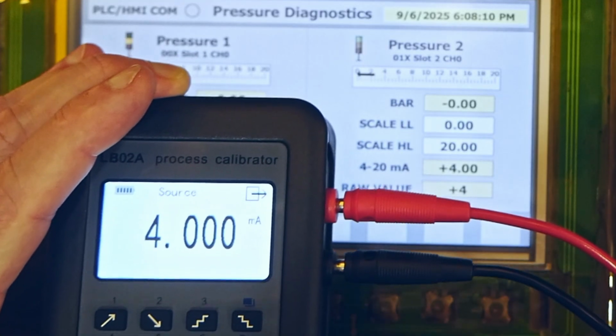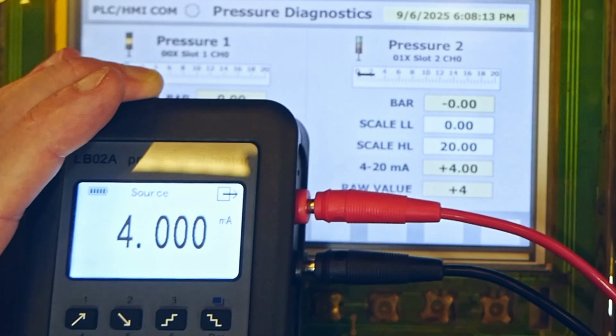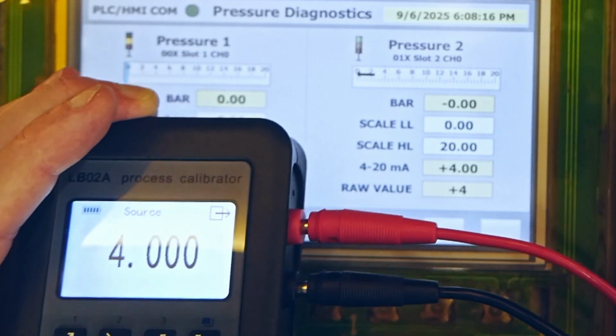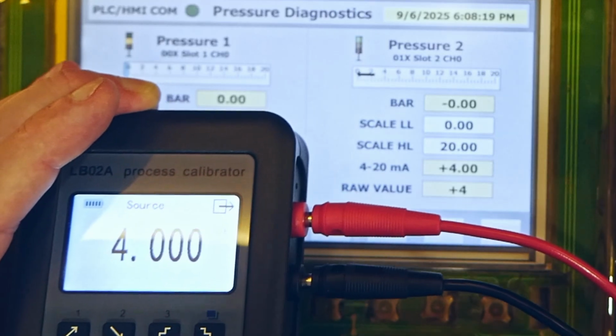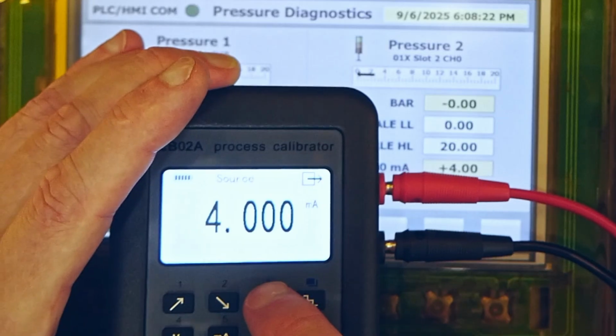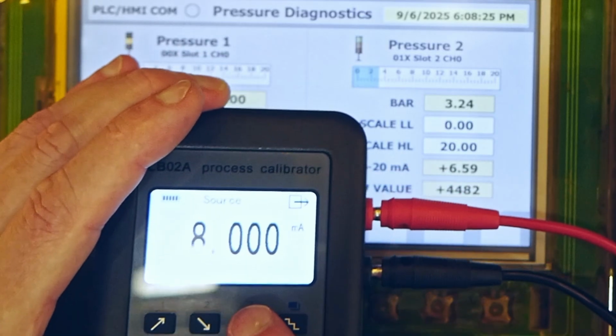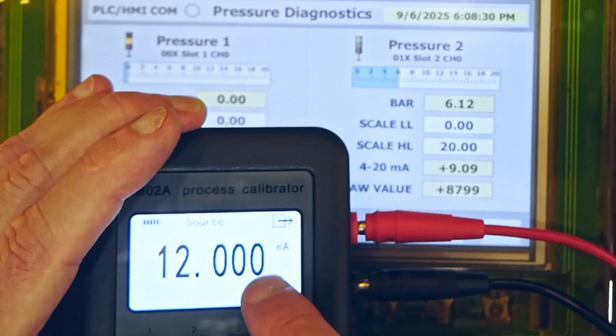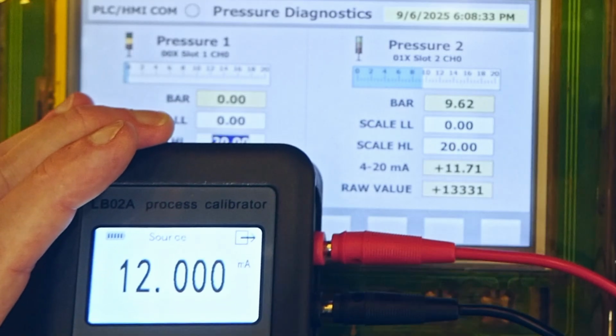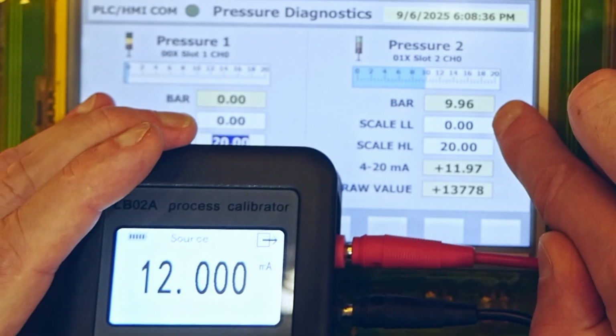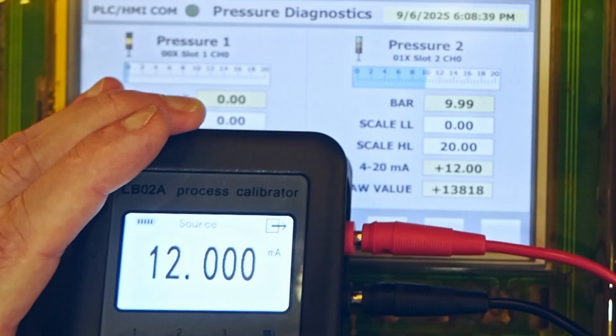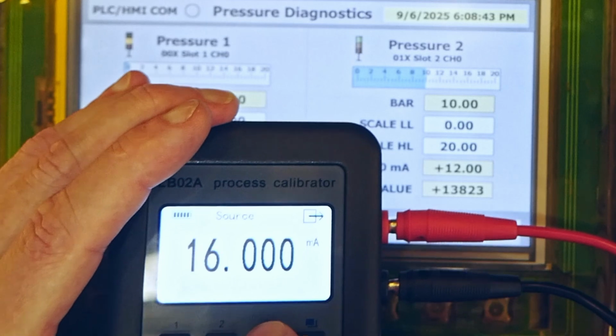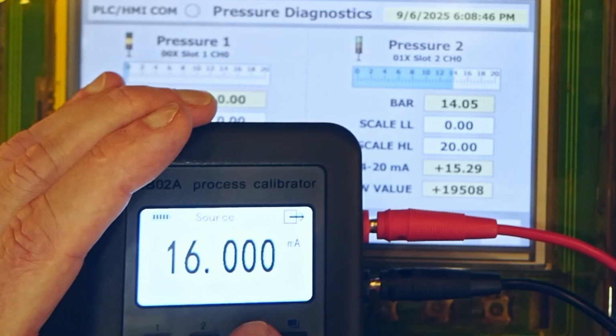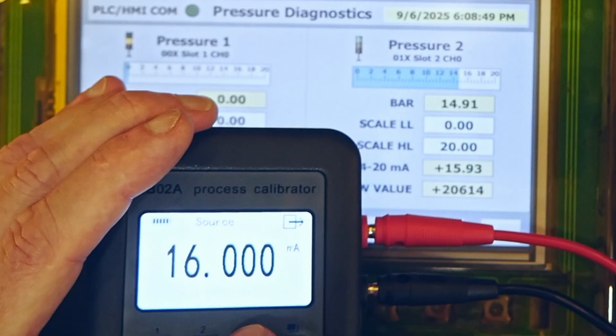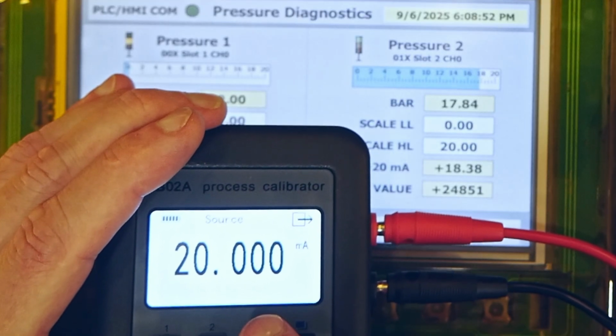We can diagnose if there is an issue, where the issue is, in PLC, in analog input card, or in wires, or in sensor. So right now I will jump to 8 milliamperes. I will go to 12. 12 is exactly in the middle. So as you can see, we are seeing 9.99. So yeah, 10 works fine. We go to 75%. And we can go to 20.